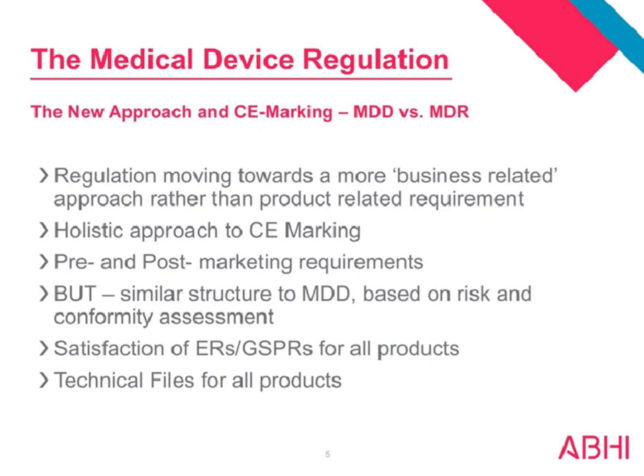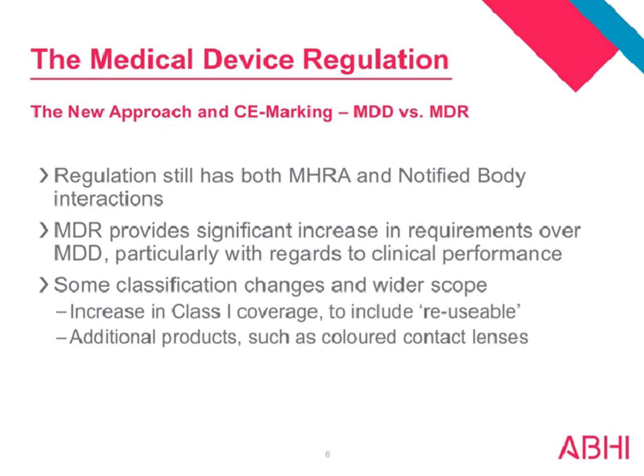But there are similarities with the Medical Device Directive. If you're familiar with the Medical Device Directive, which is based again on risk and conformity assessment, you're going to know the basic principles of the Medical Device Regulation. In both instances, you are satisfying, as we've previously mentioned, a set of essential requirements or general safety and performance requirements, and that's for every single product. And of course, every product will have a technical file generated for it. The regulation still has both MHRA and notified body interactions, and we'll talk about what those different interactions are in a moment.